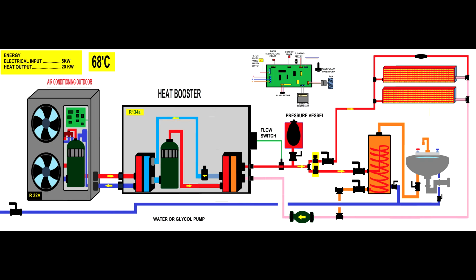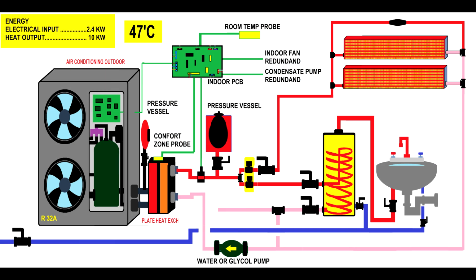That's bad. And the thing is extremely easy. What I did, I cut the pipes from the boilers, and I fit this pipe onto my heat pump. You see, I put back the first version I did without a booster, and I managed to get out from 2.4 kilowatts electricity consumption, 10 kilowatts heating.